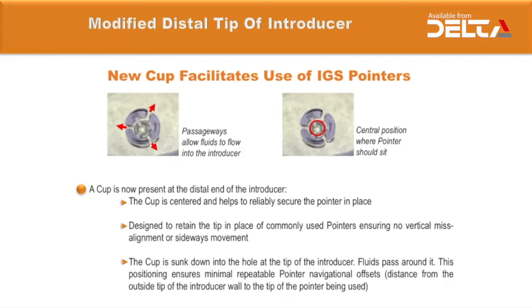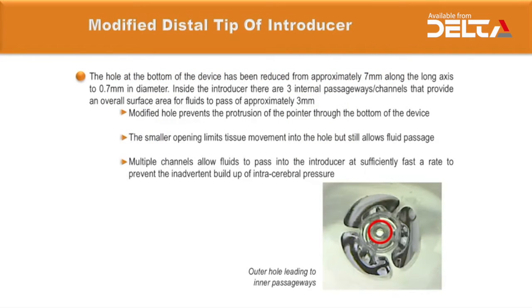The Cup is sunk down into the hole at the tip of the introducer so that fluids can pass around it. This positioning ensures minimal, repeatable pointer navigational offsets. The hole at the bottom of the device has been reduced from 7mm along the long axis to 0.7mm in diameter.